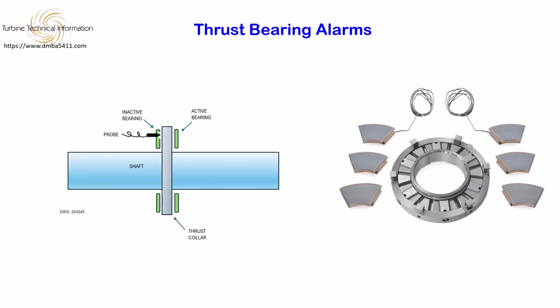How it is set up. The setup of a thrust channel depends on the specific machinery, but the goal is always to provide protection. There are two common methods. The centering method: the thrust collar is physically moved to the center point between the active and inactive bearings. The system is then calibrated so this central position represents zero DC voltage.